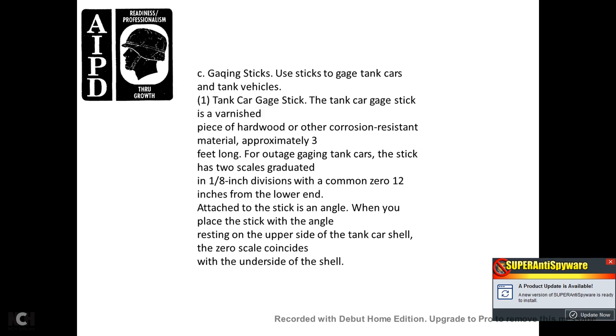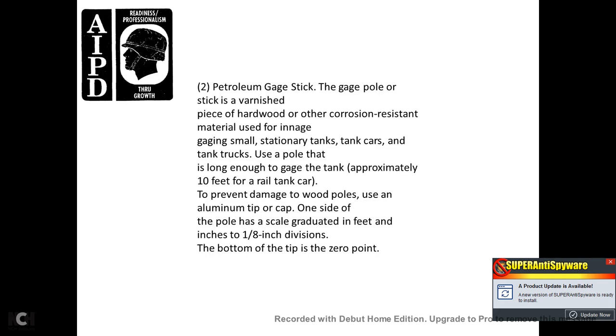14. Gauging sticks. Gauging sticks are used to gauge tanks, tanker cars, and tank vehicles. The tanker car gauge stick is varnished from a piece of wood or other corrosion-resistant material, approximately three feet long, used for outage gauging of tank cars. The stick has two scales graduated in one-eighth-of-an-inch divisions with a common zero twelve inches from the lower end. An angle is attached to the stick; when placed with the angle resting on the outside of the tanker car shell, the zero scale coincides with the underside of the shell.